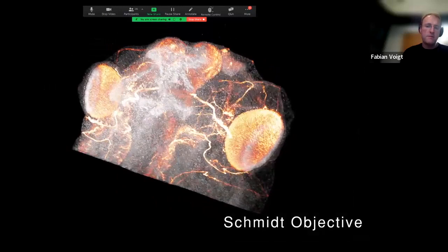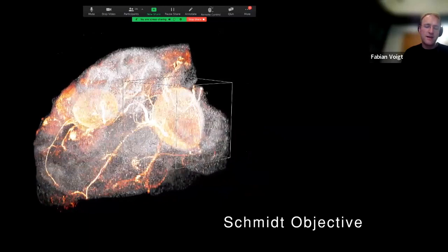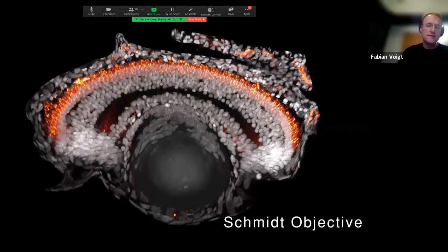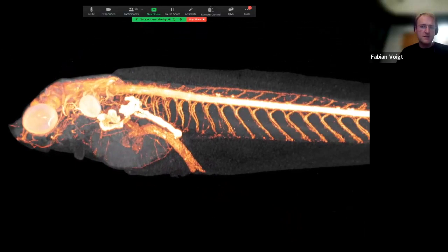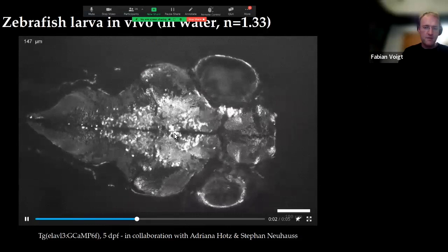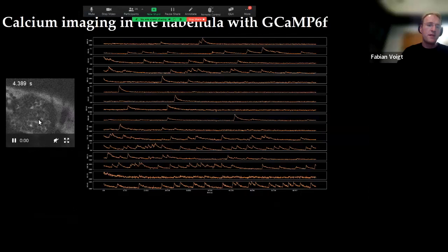This demonstrates imaging across scales — placing high-resolution data in the context of a low-resolution overview, where the overview is super fast to acquire and the high-resolution two-photon data takes a bit longer. You can also image living samples in water: a living zebrafish larva and calcium imaging in it. So the system works across a wide range of media. I'm finally coming to the end. Plotting working distance versus numerical aperture in air for current generation commercial objectives, the Schmidt objective sits a little bit outside the existing boundary. This is because by using mirrors combined with aspheres I open up a completely different design space, choosing very carefully which aberration battles to fight.